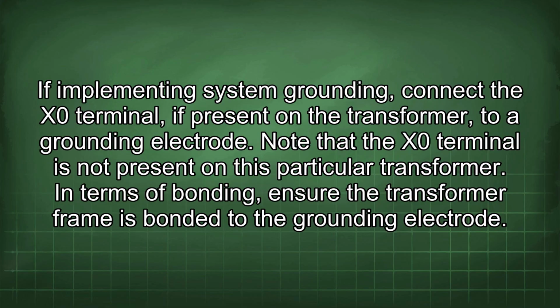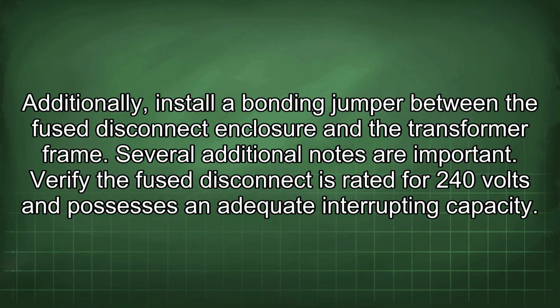If implementing system grounding, connect the X0 terminal, if present on the transformer, to a grounding electrode. Note that the X0 terminal is not present on this particular transformer. In terms of bonding, ensure the transformer frame is bonded to the grounding electrode. Additionally, install a bonding jumper between the fused disconnect enclosure and the transformer frame.